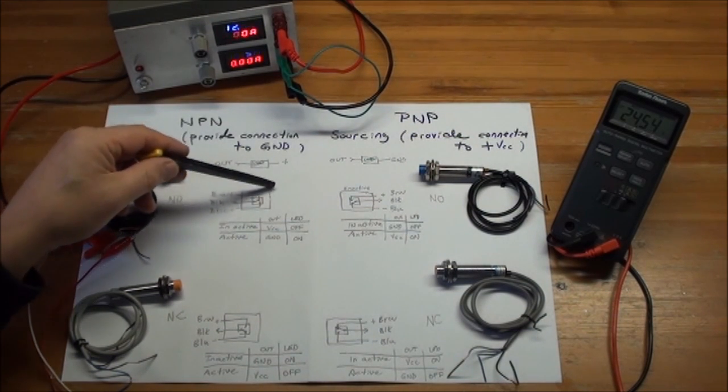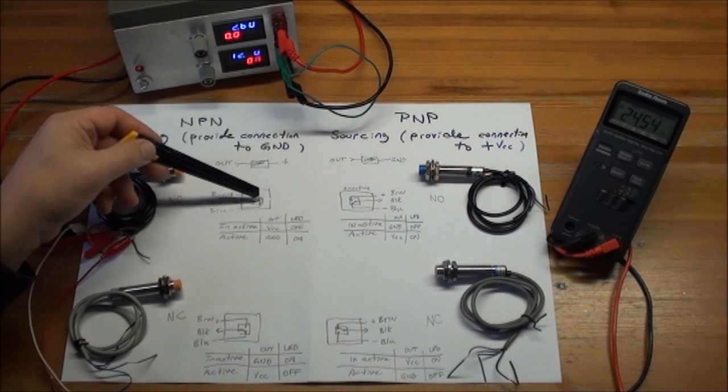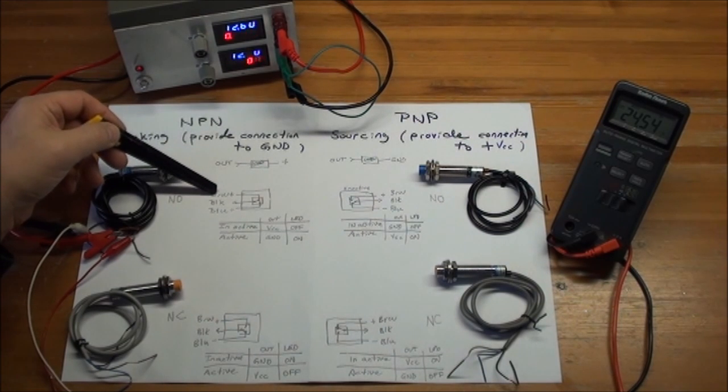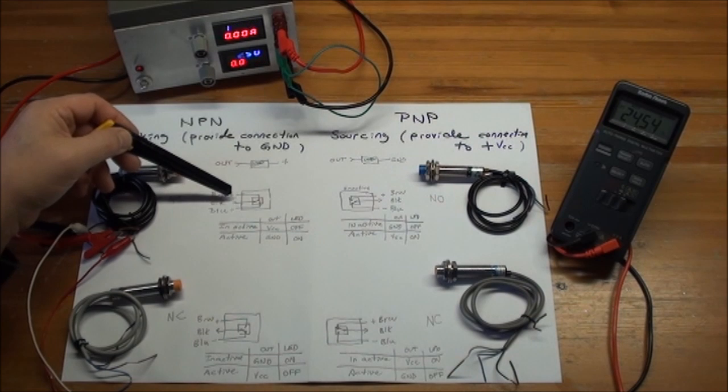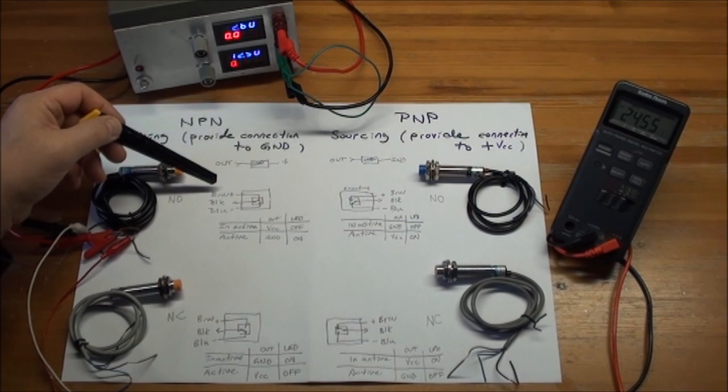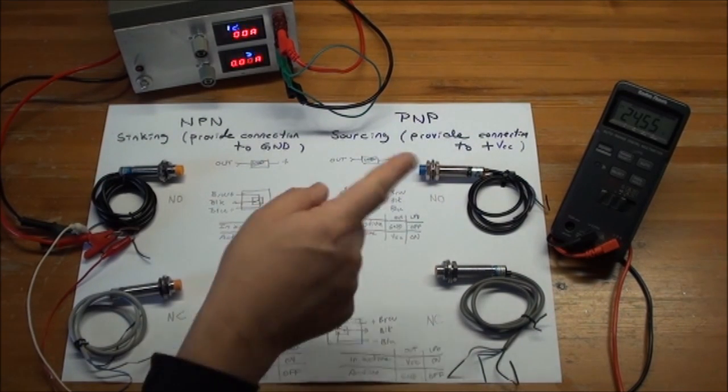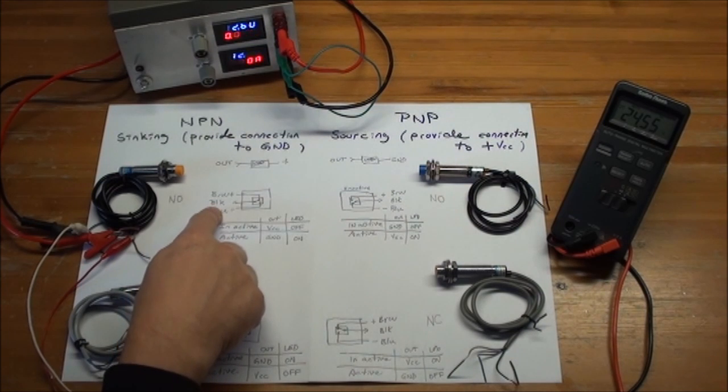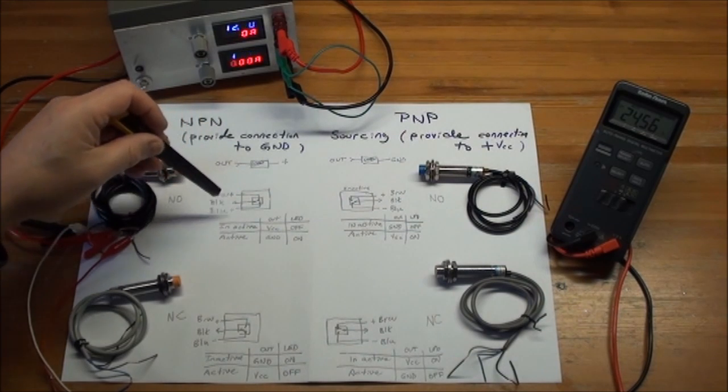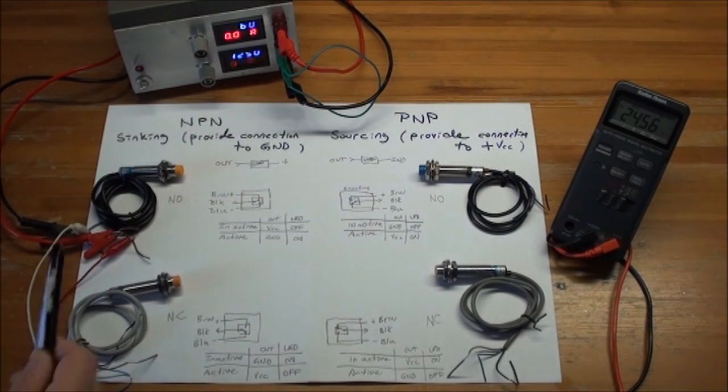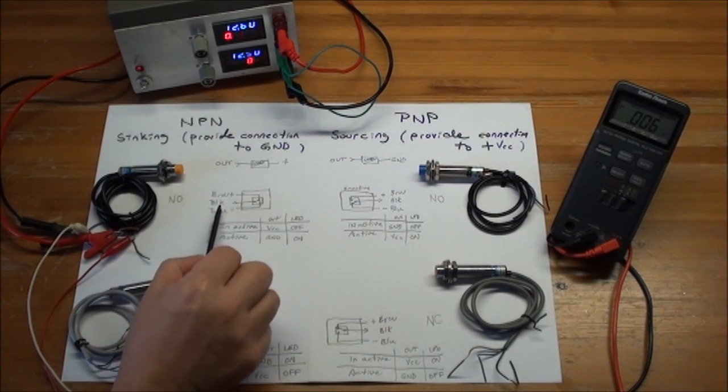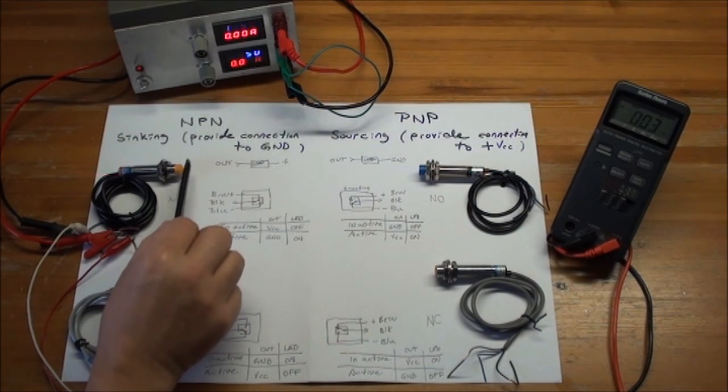If you look inside, you can envision it as a switch that goes up and down between the different wires. You have the brown being plus, the black being the out, and the blue being the minus. And in the state that it is right now, you have the 24 volts coming out of the black. So you can envision that you have a connection from brown coming out of black. Then when activated, the switch goes down and you get zero, which is the same as you have a connection to ground. So that's how this one is working.